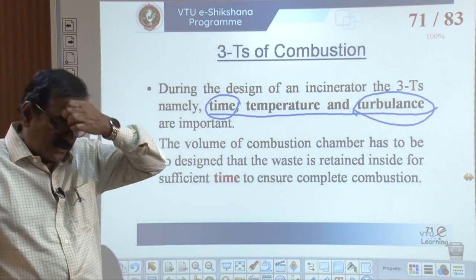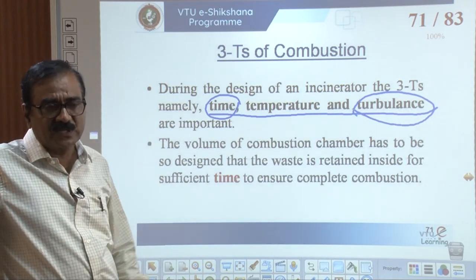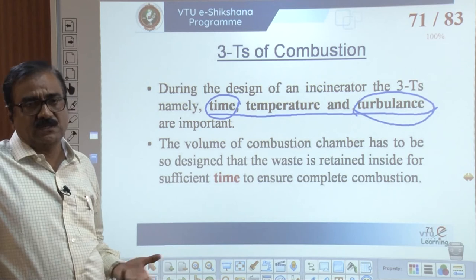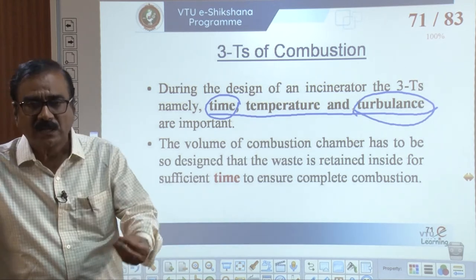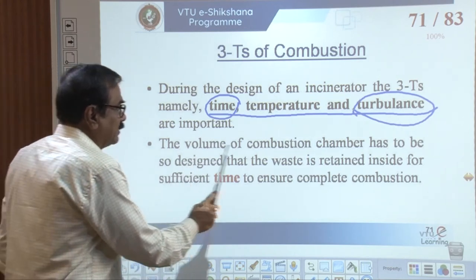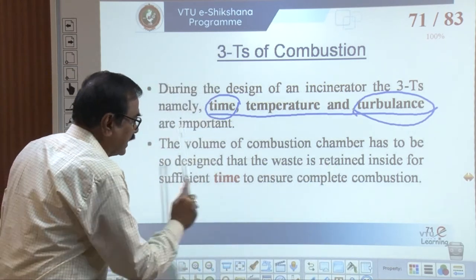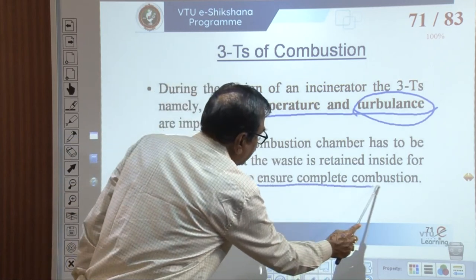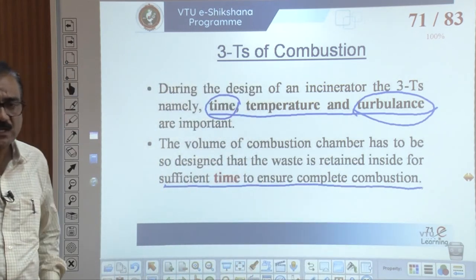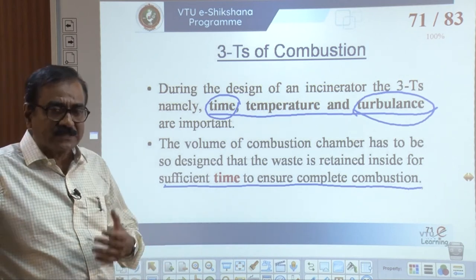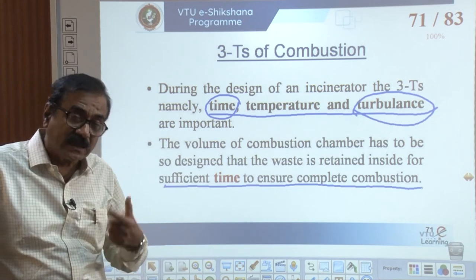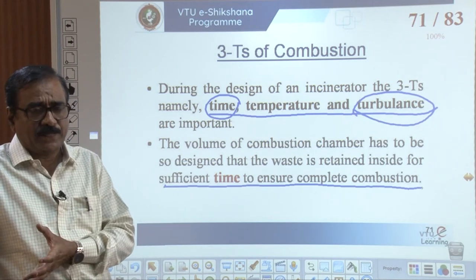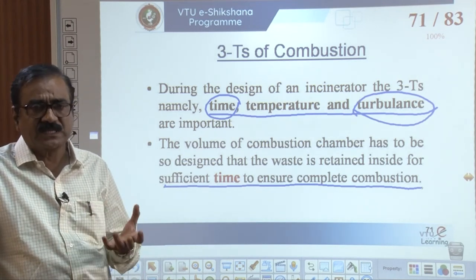Once you are subjecting a mixture of commingled solid waste for burning, the efficiency of combustion will depend upon time, temperature, and turbulence. The volume of the combustion chamber has to be designed such that the waste is retained inside for sufficient time to ensure complete burning. Sufficient time is obviously required — anything needs enough time to burn effectively. If the time is very short, much of the organic fraction of the waste goes unburnt, leading to further problems.